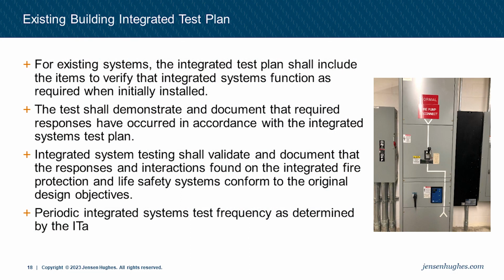There's also requirements for an existing building integrated testing plan. For an existing system, the integrated testing plan needs to verify that the integrated systems function as required when initially installed. Testing should demonstrate and document that the required responses have occurred in accordance with the plan. The integrated system test shall validate and document that the responses and interactions conform to the original design objectives and code requirements. And then there's the periodic integrated system testing.